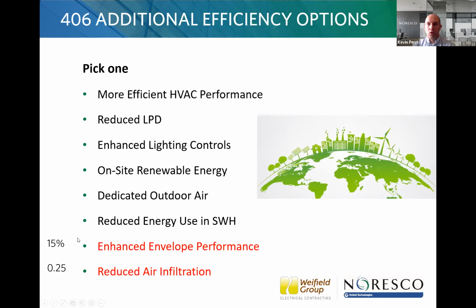And if you're not familiar with what was added in the last code cycle, these little percentage values will give you a little hint. So remember, Denver had a 0.40 air infiltration requirement for testing. Well, if you want to pick that as one of your 2 options, you have to have a better value. So it would be 0.25 CFM of envelope leakage. And then also on this enhanced envelope performance, if you want to pick that as your option, it would have to be 15% better than the code. All the other 6 items have not changed in terms of percentages that you have to have on code.